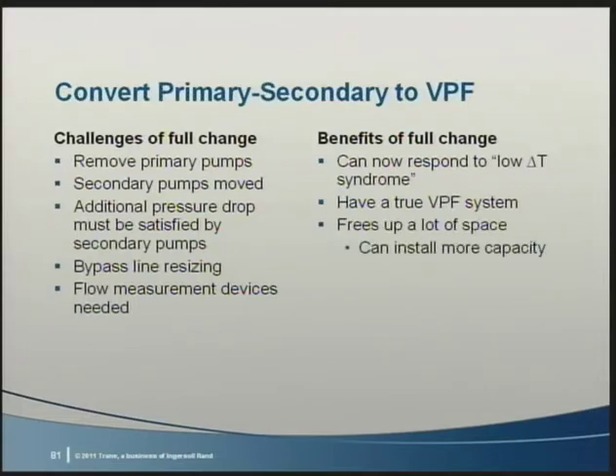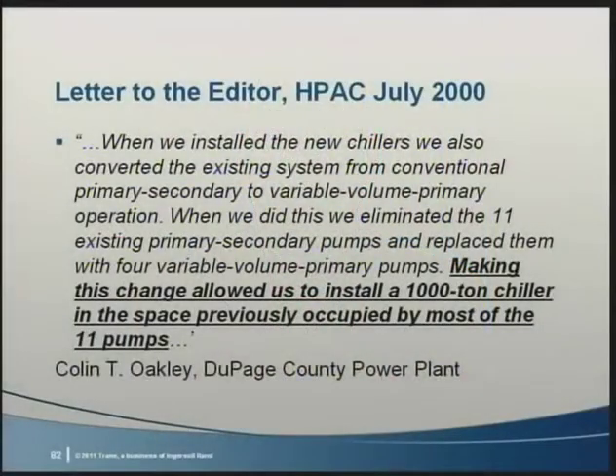After Brenda Bradley and I published an article on VPF more than 10 years ago, we received the following response in a letter to the editor. Simply put, the VPF system ends up with a lot less space needed for pumps. In this case, allowing an additional 1,000-ton chiller to be installed in the space that used to be occupied by all those primary pumps. I was once told after an entire system reconstruction that they had, quote, a mountain full of pumps to discard after totally converting their system.